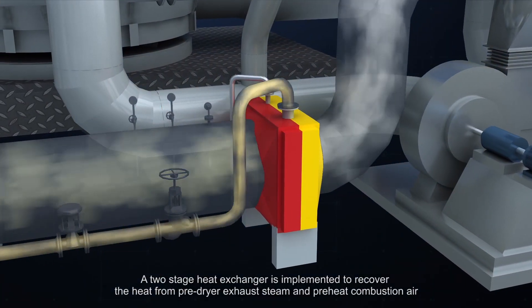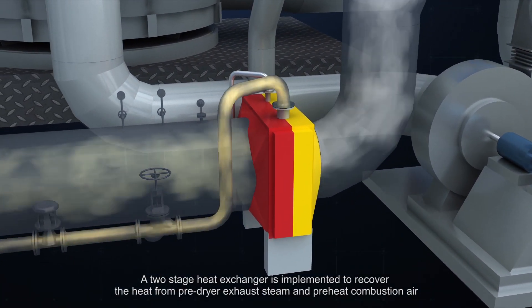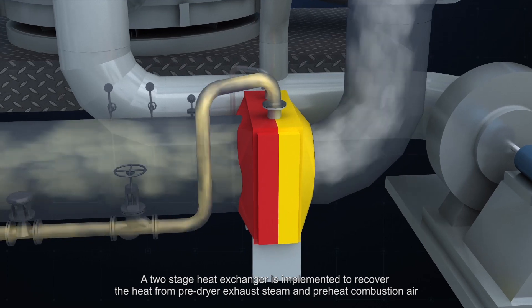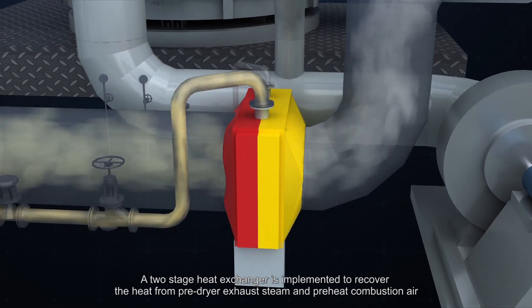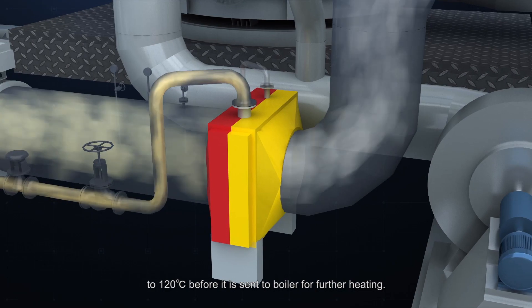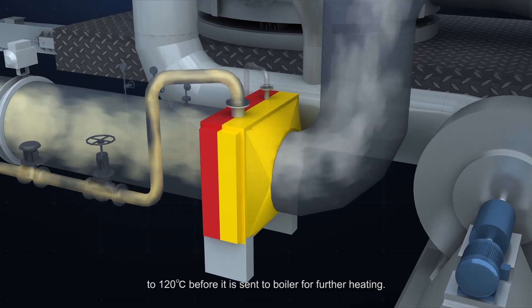A two-stage heat exchanger is implemented to recover the heat from pre-dryer exhaust steam and preheat combustion air to 120 degrees Celsius before it is sent to the boiler for further heating.